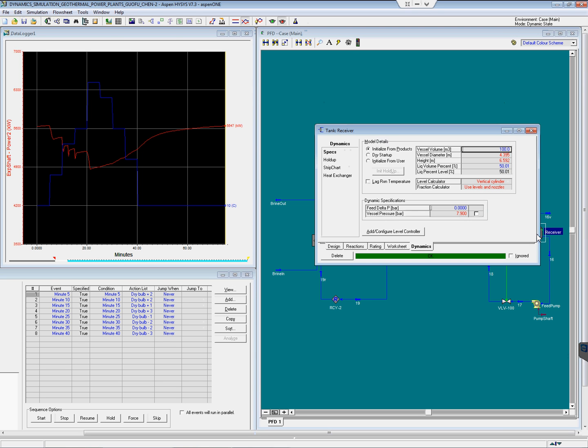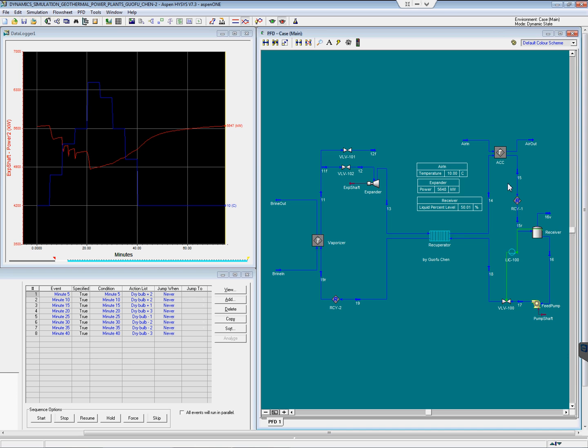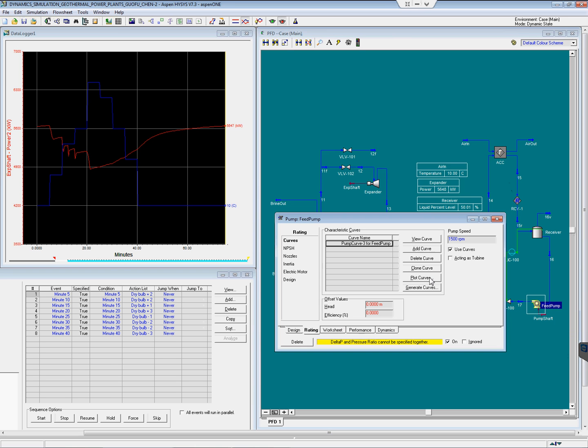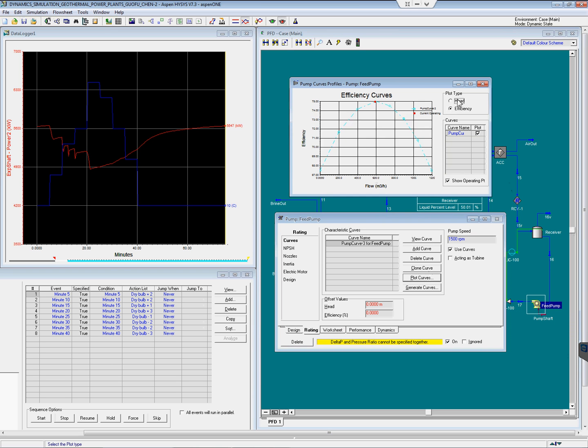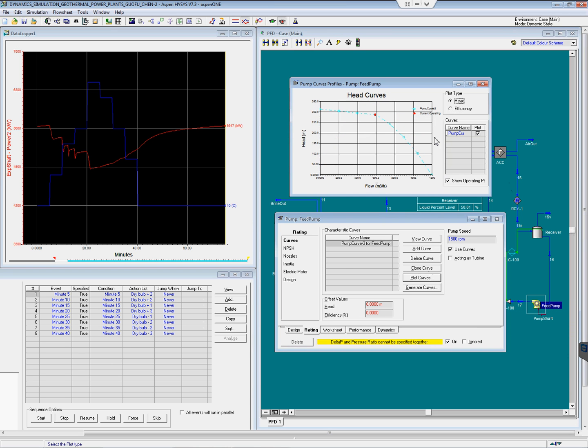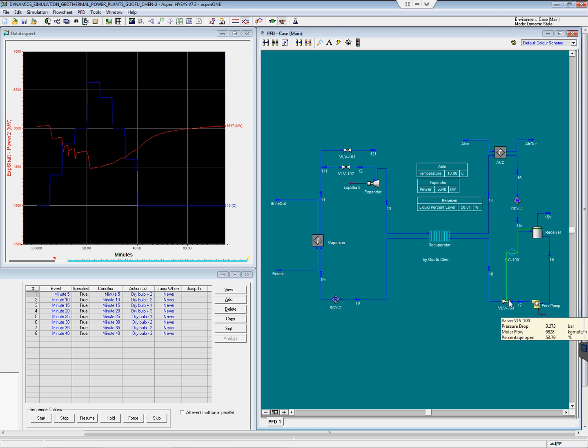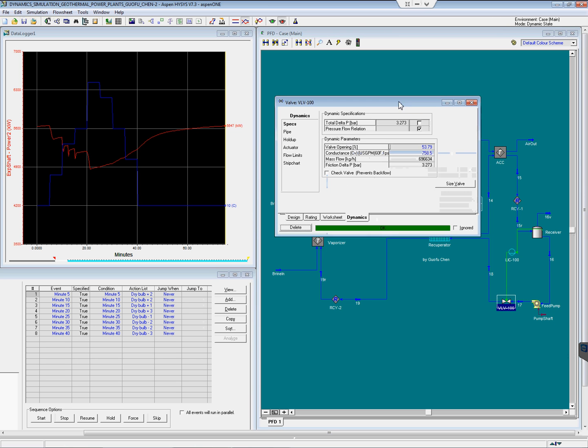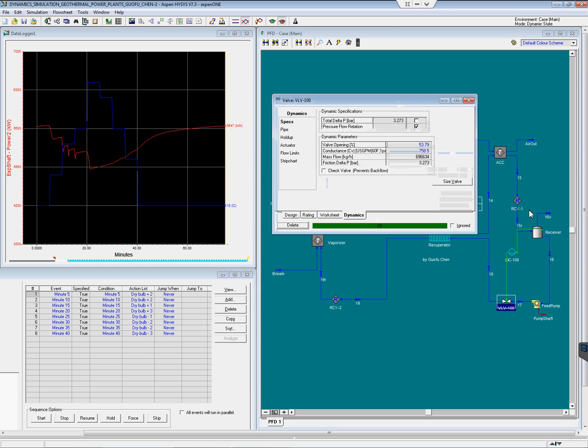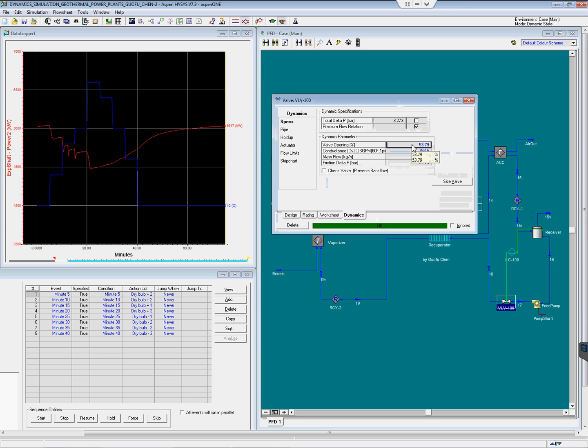The receiver has a total volume of 100 cubic meters and the current liquid level is 50%. Feed pump is rated based on the pump characteristic curve. The valve to control the liquid level at the receiver has a CV of about 759 and the current opening is about 54%.